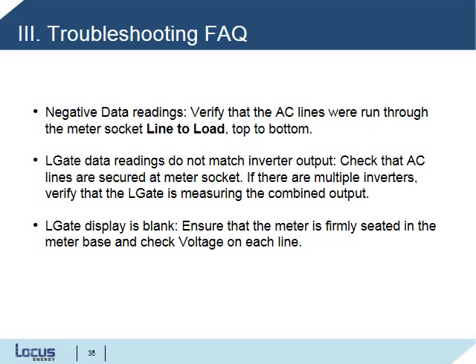The second case is if the LGate data readings do not match the inverter output. In this case, we recommend checking that the AC lines are securely connected to the tabs at the meter socket. If there are multiple inverters, verify that the LGate is measuring the combined inverter output. Finally, if the LGate LCD screen is blank, ensure that the meter is firmly seated in the meter base and check the voltage on each line. We also recommend checking that there's no corrosion or sediment in the meter socket tabs, as this can prevent a secure connection.